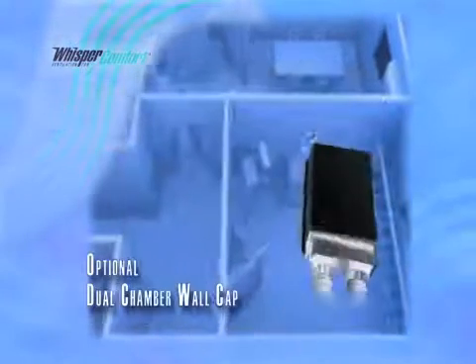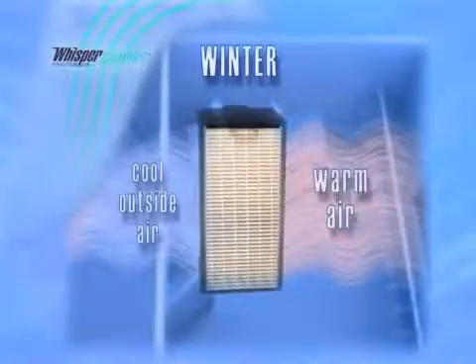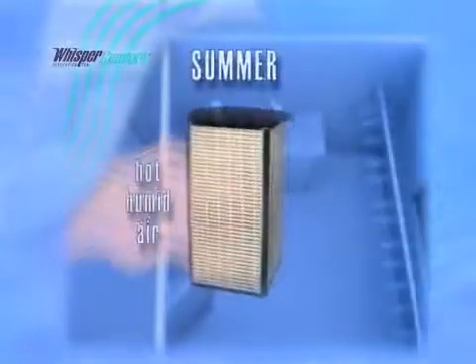Additionally, in the winter, when cool air is brought in from the outside, the capillary core transfers heat and moisture to the supply air coming into the house, helping to keep the indoor air warm without becoming too dry. The opposite happens in the summer, when it helps to make the hot humid air from outside cooler and drier before it enters your living space.